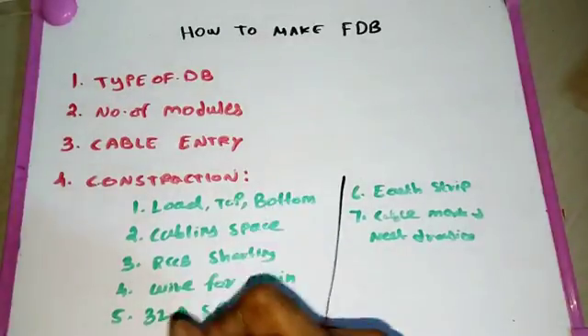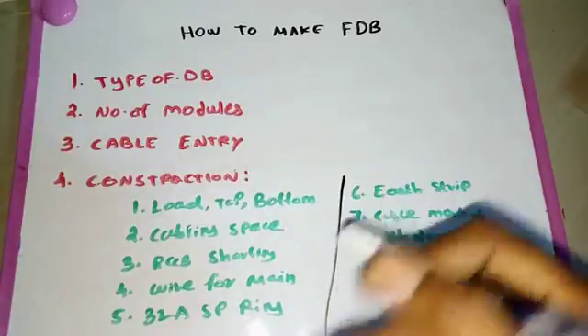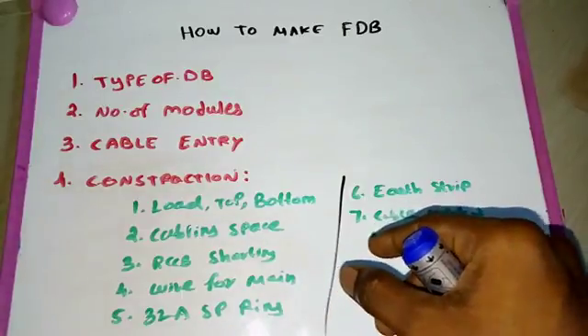When constructing the DB, the first factor is the load. Based on the load, we decide whether to place the breaker at the top or bottom. For example, lighting loads are mostly at the top, so the lighting breakers should be placed at the top. Socket breakers should be placed at the bottom. This determines the arrangement of breakers in the DB.